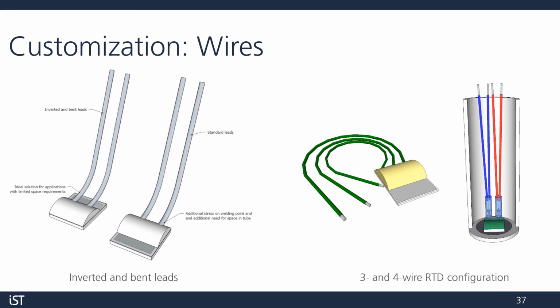In the example on the far right, we take this a step further. We take a sensor with two leads, then laser weld 4 lead extensions, 2 on each. Now we can compensate for all wires right up to that laser welded extension point.